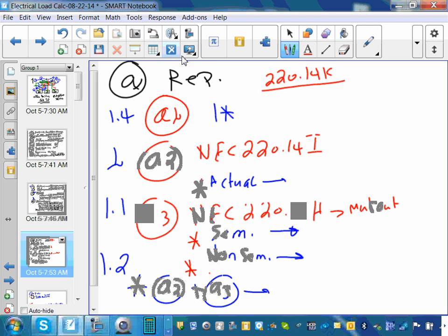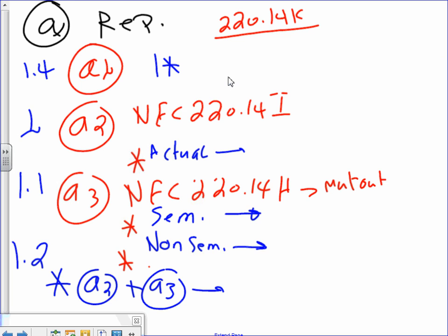Let's go back to where the 1 volt amp comes in. So you take 1 volt amp, what's the square foot of the building? 50K. When you multiply one by 50, guys, you forget your math, what do you get? 50K, K what? Kilovolt amp. We size everything based on volt amp. So it's so important, guys, to use the word KVA, not KW. KVA.